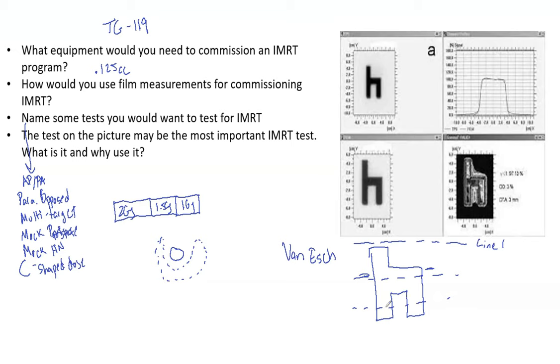Profile three shows no dose between the legs of the chair: dose here for one leg, dose here for the other leg, but nothing in between. The MLCs are really tested in their accuracy — they have to work perfectly in sync together to produce a clean chair pattern. Not only does the chair test measure interleaf leakage, homogeneous dose, and the chair pattern itself, but any MLC errors will produce a mismatch visible in this test — which is why it's so important.